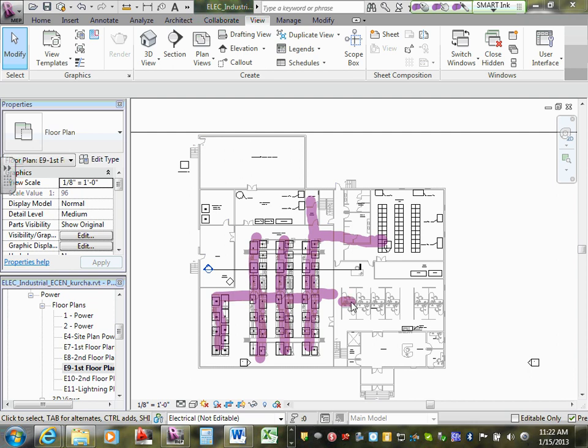So what we typically did is ran one right to the top of the office, and then also grab this one right here. This is something similar to how we put the cable tray. One way. Everybody can see that. You need to capture the data from all these machines. So you put it right to the top of the machines and you capture them. Does that make sense? So that's one way. It doesn't have to look like this, but that's one way you capture the info from the office right here, from all these machines, take it to the telephone room as well as the data. So that's our data. And the reason why we stop here is because you're underfloor here, it goes down, you can pick things from underfloor.